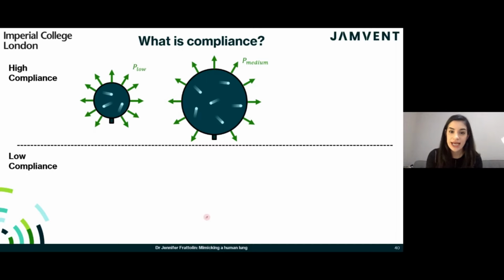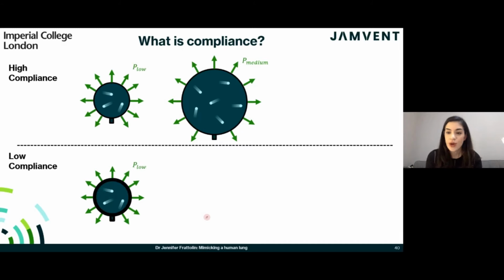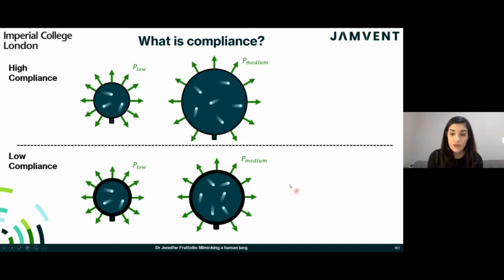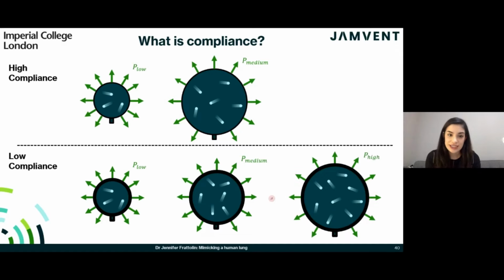But what happens if we have a thick-walled balloon? At that same low pressure, the balloon will expand to that same volume. However, as we start to increase that pressure, you'll notice that because the thick-walled balloon has a higher stiffness, the actual amount that the balloon inflates for a similar pressure is less than that thin-walled balloon. That's because of its lower compliance in comparison to the thin-walled balloon. And so we would need a higher pressure in order for it to inflate to that same size as the thinner balloon.